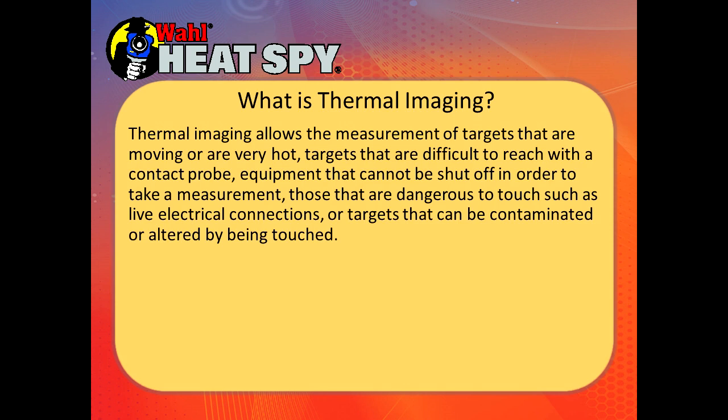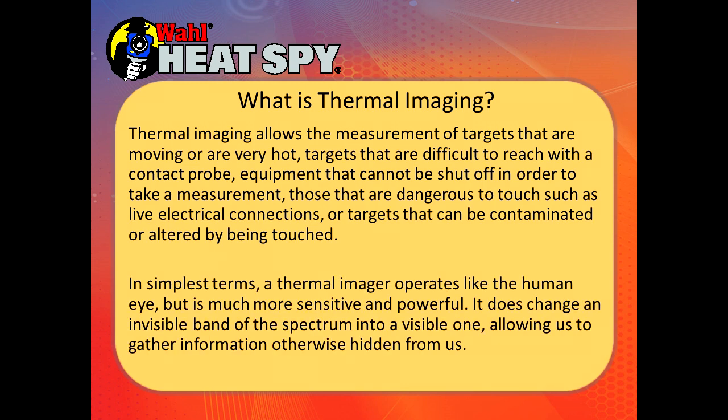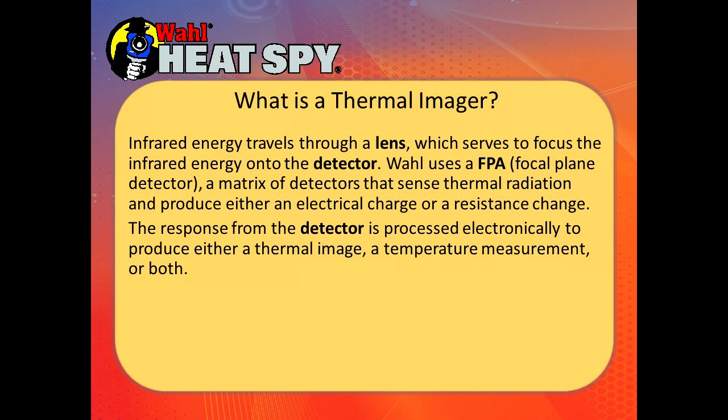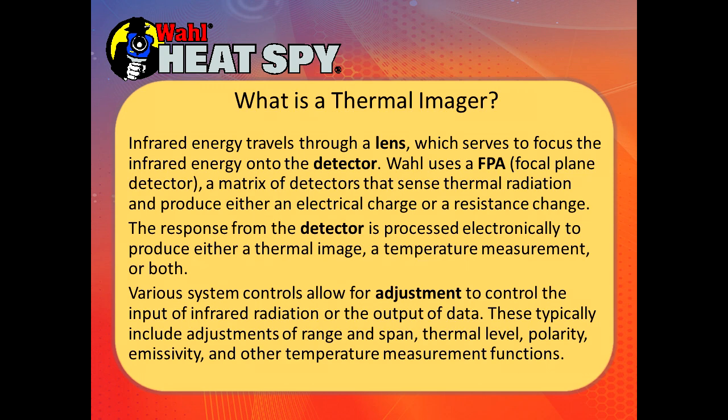Thermal imaging allows measurement of targets that are moving or very hot, targets difficult to reach with a contact probe, equipment that cannot be shut down for measurement, those that are dangerous to touch such as live electrical connections, or targets that can be contaminated or altered by touch. In simple terms, a thermal imager operates like a human eye but is much more sensitive and powerful. It changes an invisible band of the spectrum into a visible one, allowing us to gather information otherwise hidden. Infrared energy travels through a lens which focuses it onto a detector — Wahl uses an FPA focal plane array detector that produces either an electrical charge or resistance change.